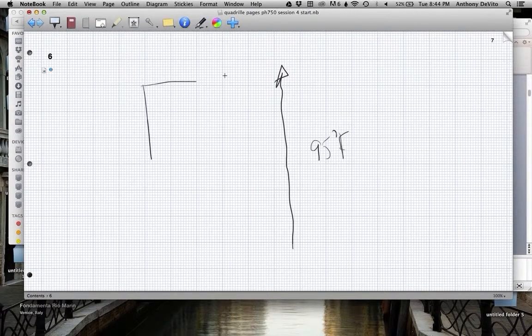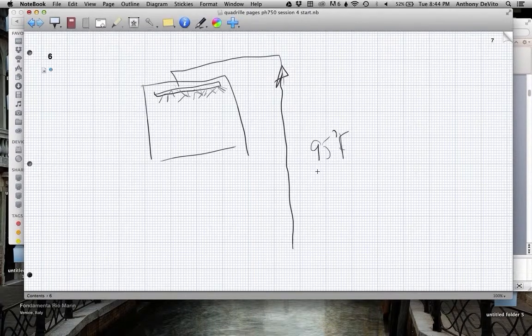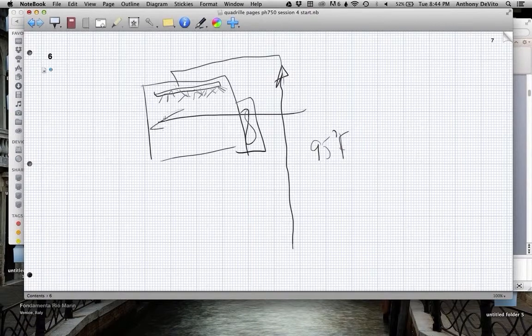There are boxes on the roof of many of these buildings or in the parking lot or wherever where you take that water, you send it up to this device, and this device has a spray header in it, a big pipe with a bunch of spray nozzles in it. And it takes that water and sprays it into this box. At the same time that you're spraying the water into this box, you're blowing air across it. Tons of air. Now, what does the air do to that water?